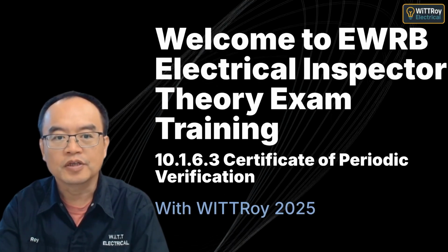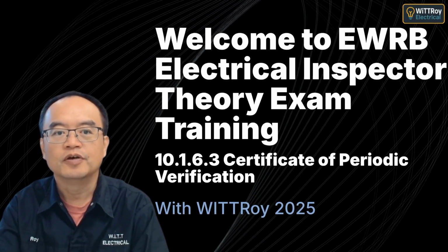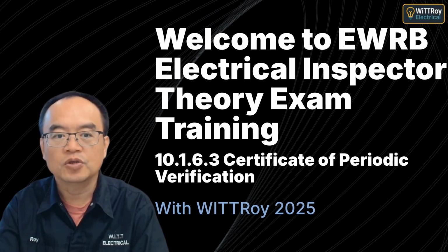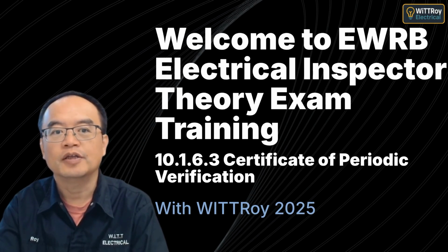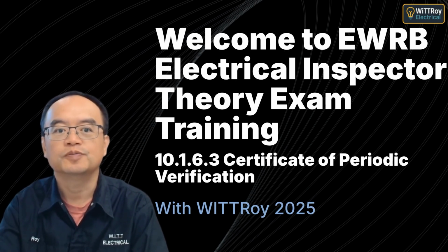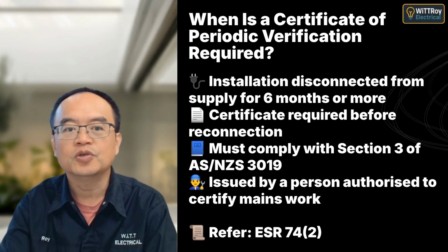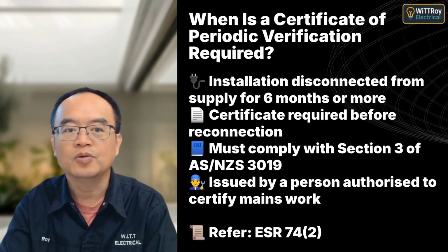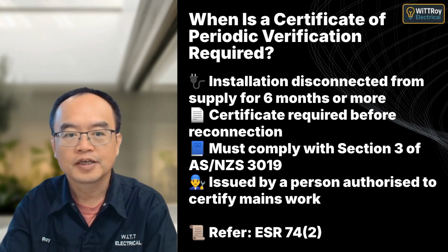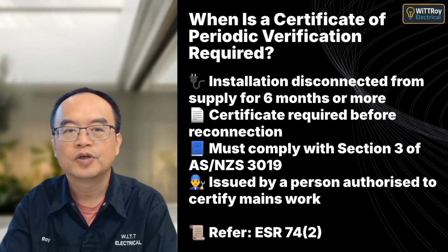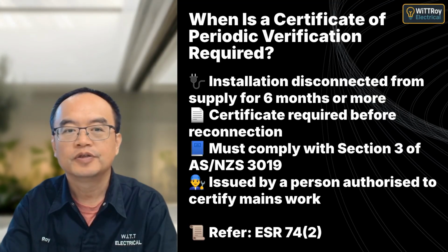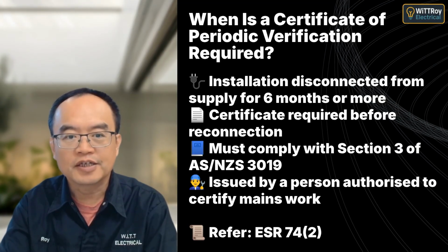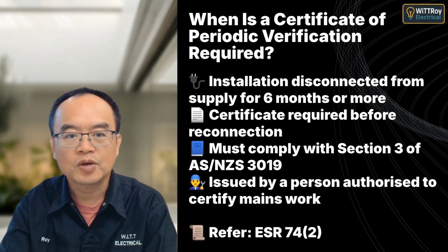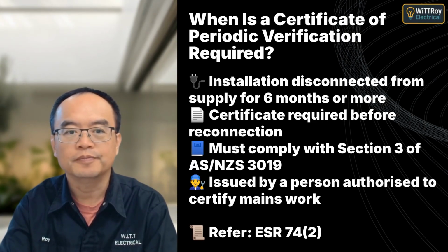In this lesson we're looking at 10.1.6.3 Certificate of Periodic Verification. You'll learn when this certificate is required and who is authorized to issue it. If an electrical installation has been disconnected for more than 6 months, it cannot be reconnected without a certificate of periodic verification. This must follow AS/NZS 3019 and be signed by someone qualified to certify mains work.